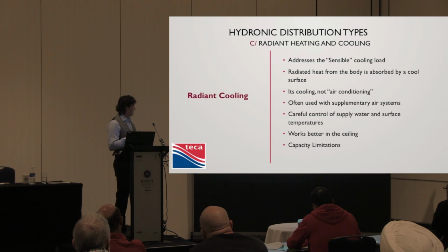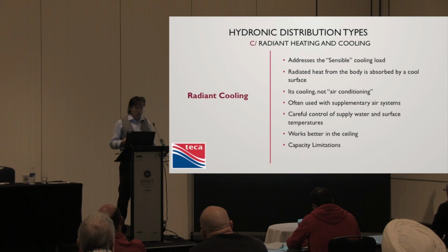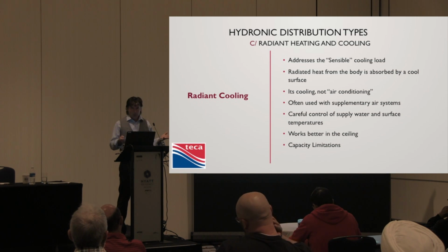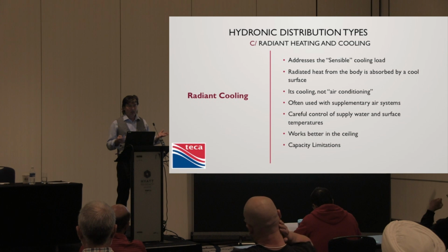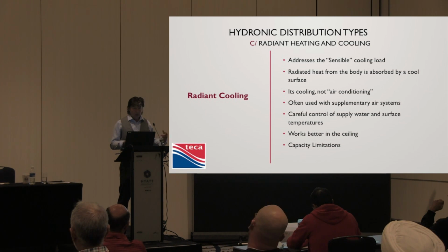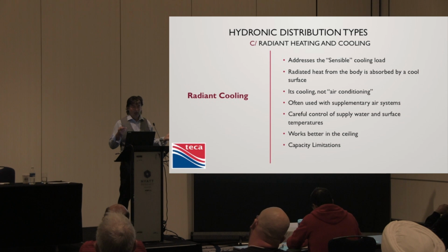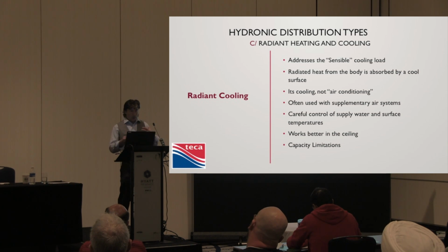So it requires very careful control of supply water and surface temperatures. Heaven forbid we should actually cross the dew point with our relationship of our supply water temperature and the air temperature, the humidity level, and therefore the dew point. We do not want to send 45-degree water around a floor, for example, and have the moisture in the air actually condense on the floor or anywhere. It wouldn't have to be in the floor. It could be anywhere in the structure, wherever that piping is. It could be in the wall. So very critical to control supply water temperatures.